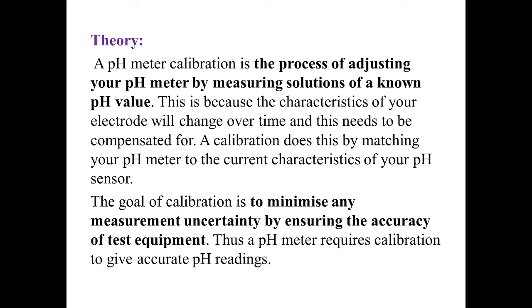So the pH meter actually consists of electrodes. In recent instruments, we have a single electrode, a combination electrode. Earlier, we used to have two electrodes. One was a reference electrode, another was a glass electrode. So what happens when you store your electrodes? They may undergo change, and hence you need to compensate for the change. A calibration process compensates for the change by matching your pH meter to the current characteristic of the pH sensor.